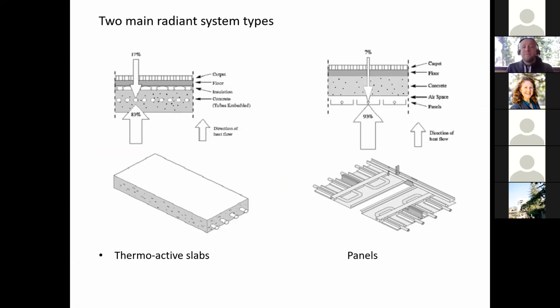Of the two system types, we use both: thermally active slabs, which I just talked about, but also radiant panels, especially if there's a concern about flexibility in the future. A radiant panel can be taken apart, moved, or added to if you need more capacity, or taken away as the program changes. So in project types where the program is going to churn a bit, we might bias towards panelized systems to provide more flexibility.